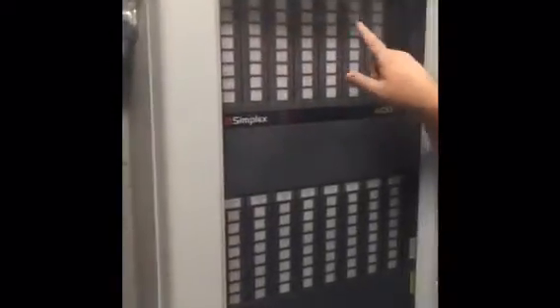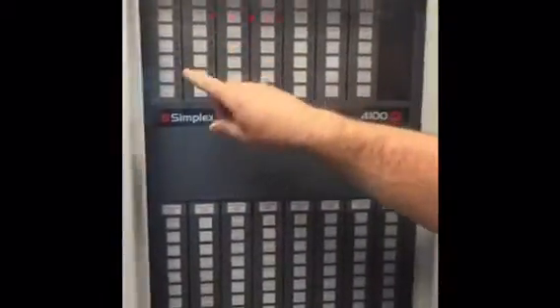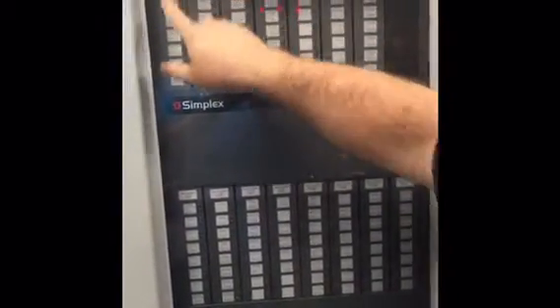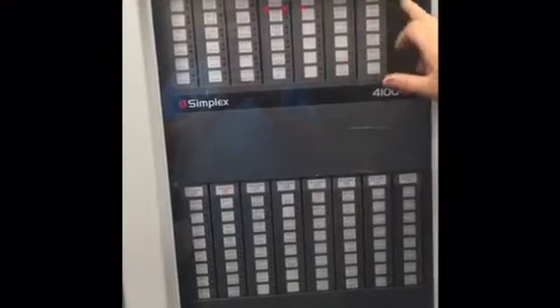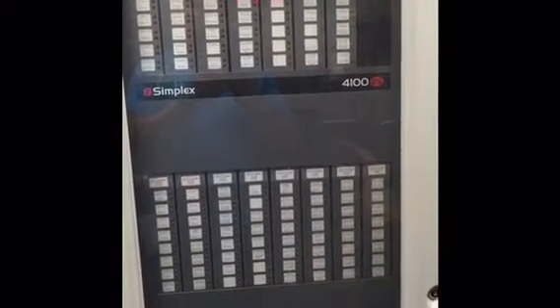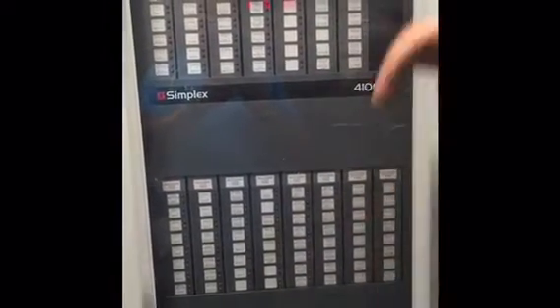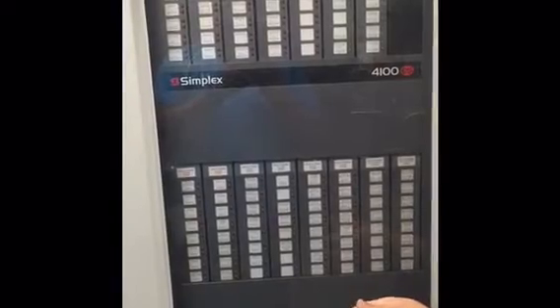Also over here on the annunciator, it's gonna light up in red telling you which area the alarms are coming from. So we would get the 5th floor red light. Here we have North Tower, over here we have South Tower alarms. So they're all going to come up on a red light telling you where the alarm is. We could get another alarm coming in at the same time. You know, we might start with the 5th floor, the smoke could rise up to the 6th and 7th, so we'll be able to see more lights, more zones go into alarm that are activated, okay?